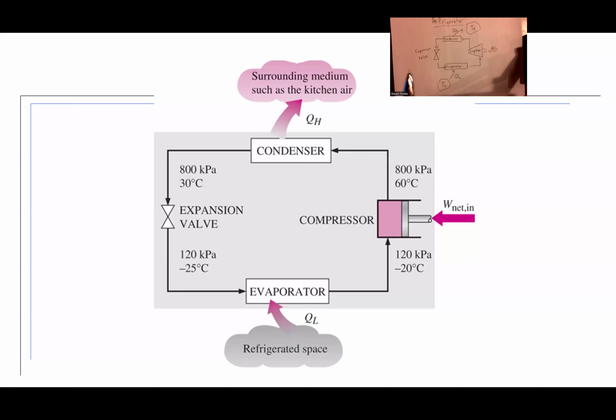The best way I know to describe the expansion valve is like a can of compressed aerosol, like computer cleaner: if you hold it open for a long period of time, it gets cold. This is the same basic principle. On this side I've got high pressure, like inside the aerosol can, and if I hold it open for a long time the pressure drops, and as the pressure drops, the temperature drops. This is the same thing, except it's a continuous flow situation.